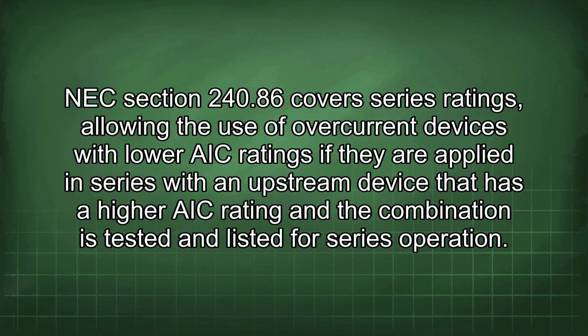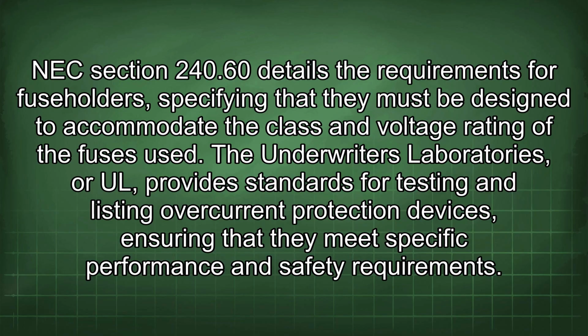NEC Section 240.86 covers series ratings, allowing the use of overcurrent devices with lower AIC ratings if they are applied in series with an upstream device that has a higher AIC rating and the combination is tested and listed for series operation. NEC Section 240.60 details the requirements for fuse holders, specifying that they must be designed to accommodate the class and voltage rating of the fuses used.